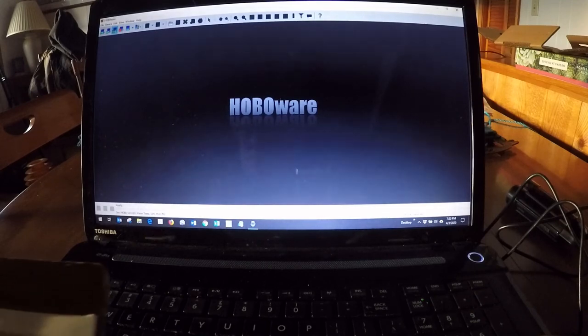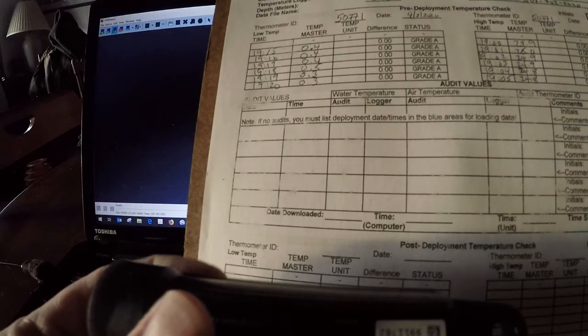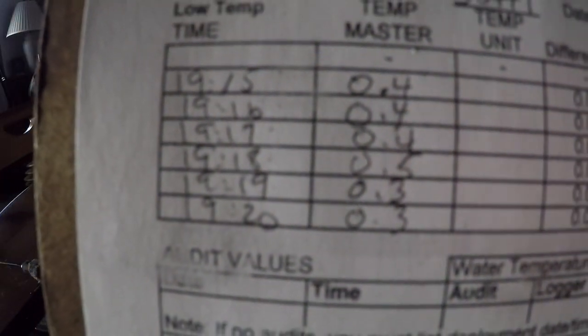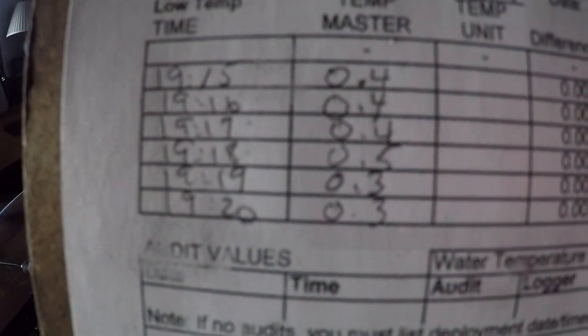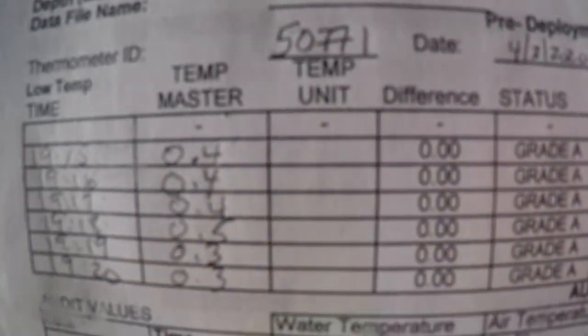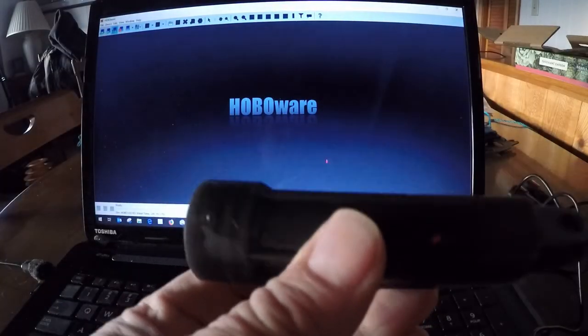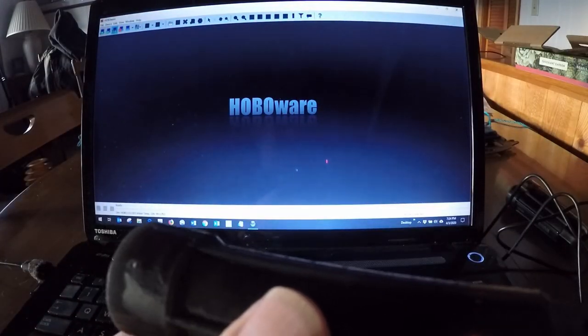Okay, so we're finished with the actual deployment in the ice bath. I pulled it out of the ice bath, and as you can see, we've got the numbers completed down to the 1920, or 7:20, when we finished. Now what we have to do is figure out the temperature units, this column here. The only way to do that is to read the data off of your temperature probe.